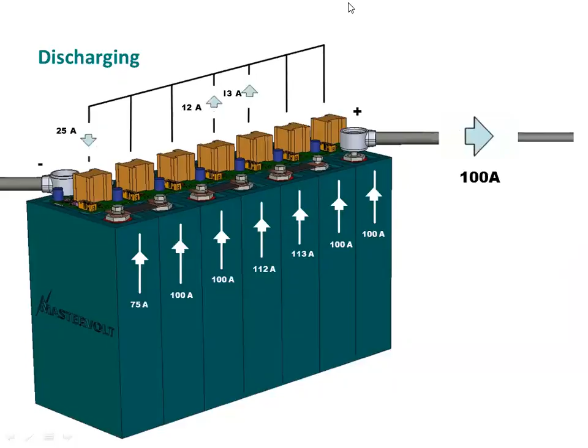So it's kind of a DC-DC converter - excess power from one cell that's filling up quicker than the others gets brought over to the other cell. I have a little animation here that shows that. So this is a battery where you're taking out 100 amps - each cell provides 100 amps, but you can see this cell was more charged, so it will supply more current at this point. That's controlled by the BMS system, and it's the same when you recharge the battery.